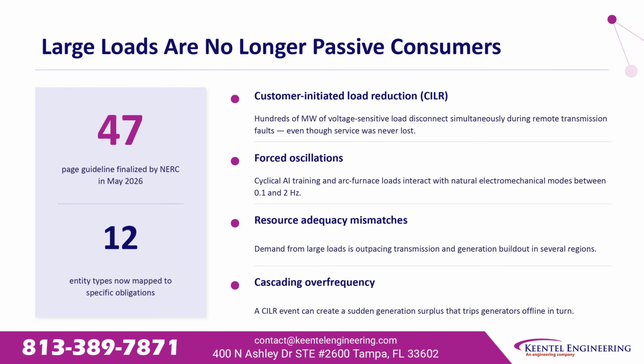The core message is simple. Large loads are no longer passive consumers. 4 failure modes drove this shift. Customer-initiated load reduction, hundreds of megawatts of voltage-sensitive load disconnecting simultaneously during a remote transmission fault, even when service was never actually lost.